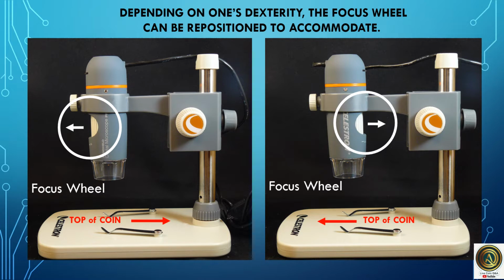Depending on one's dexterity, the focus wheel can be repositioned to accommodate. You can either face it toward you and operate it with your thumb, or it can face away from you and you operate it with your fingers. When you switch the position like this, the top of the coin will go in first, so that the top of the coin is seen at the top of the computer screen. If you turn it around the other way to use your fingers to manipulate the focus, the top of the coin will be facing you, so that the top of the coin will be at the top of the screen on the computer.